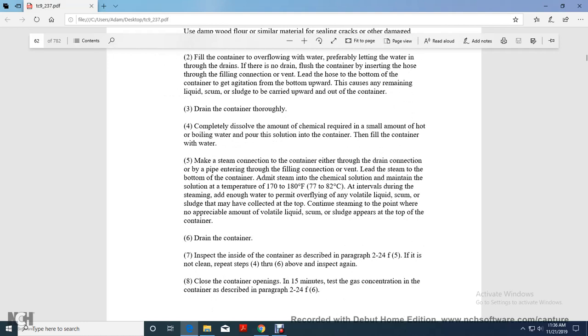Make a steam connection to the container, either through the drain connection with a pipe or by entering the filling connection or vent. Lead the steam to the bottom of the container. Admit the steam to the chemical solution. Maintain the solution temperature at 170 to 180 degrees Fahrenheit. At intervals during the steaming, add enough water to overflow any volatile liquid scum or sludge that may have collected at the top. Continue steaming until an appreciable amount of volatile liquid scum and sludge no longer appears at the top of the container.